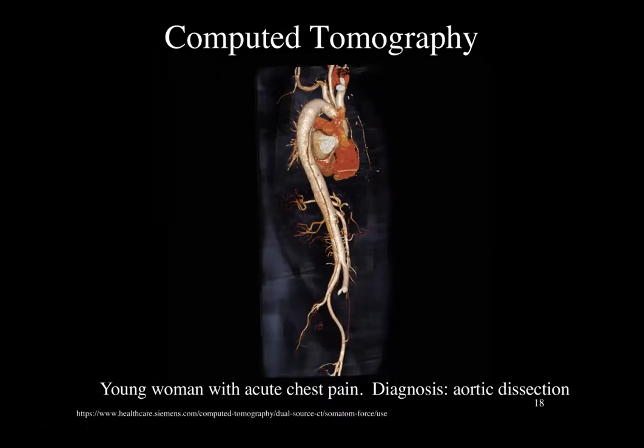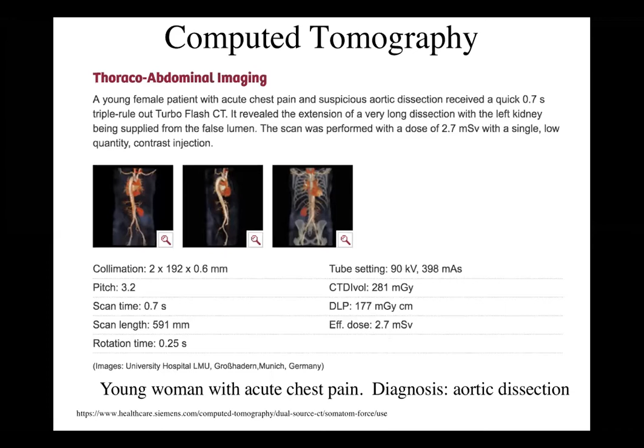Just to look at the parameters here, I was way off. The whole scan time is under a second for this, right? The scan length is half a meter. Rotation time of the gantry is a quarter second. So that means that the gantry with the source and the detector is rotating 4 times a second around the patient. And the total dose that the patient acquires from the X-rays for this exam is 2.7 millisieverts over this part of their body. Just being alive and walking around for 1 year, your estimated dose is 3 millisieverts just from cosmic rays and natural radiation from radon and things like that.